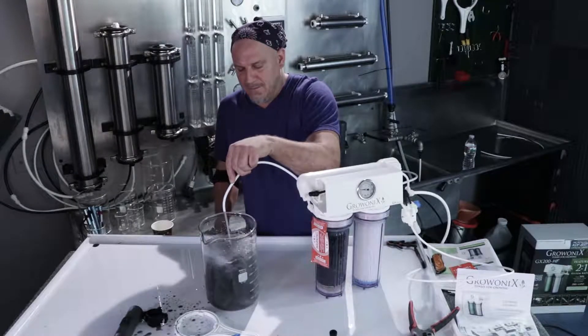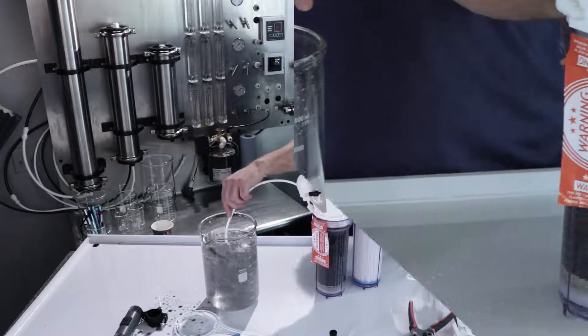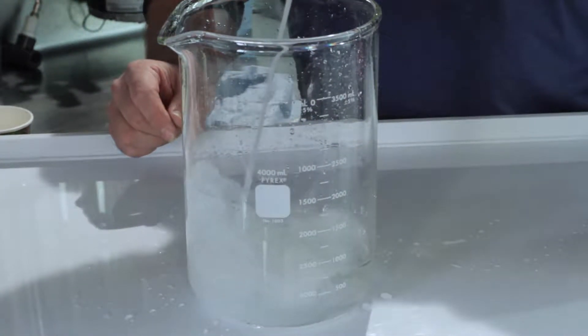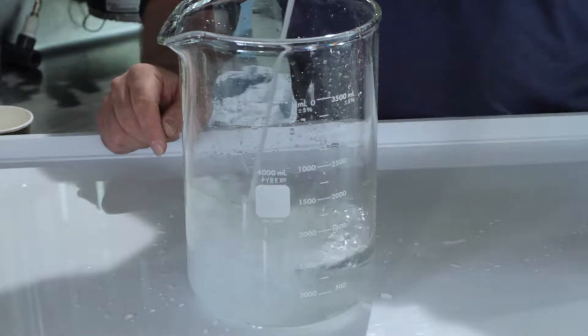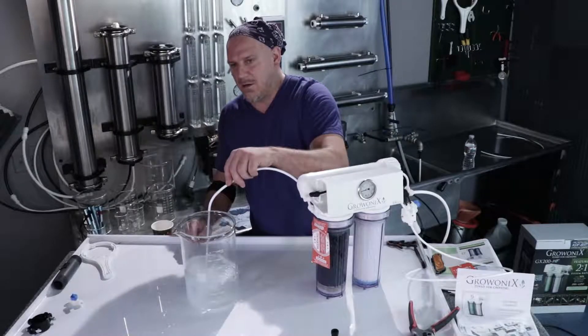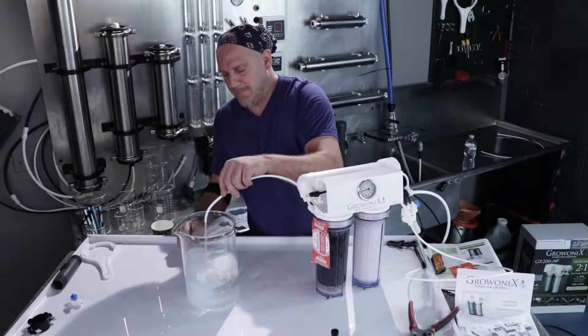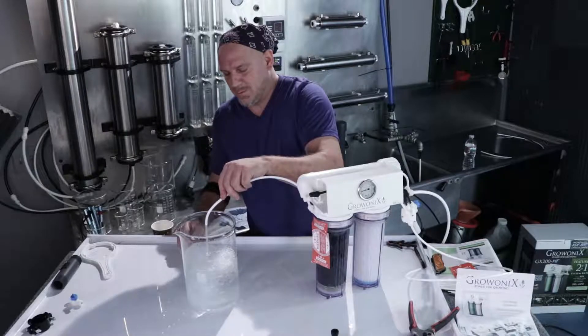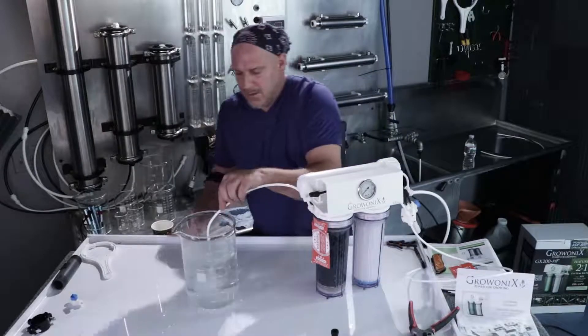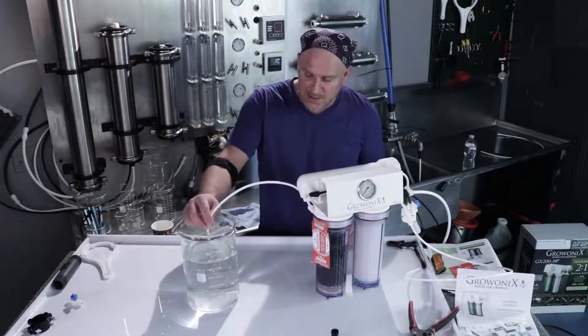You can see the stream cleaning up right now. As you can see, that stream is really cleaned up. There's a lot less air bubbles in it, it's almost perfect. I flushed about 10 gallons of water through this carbon already, and you can see the water is coming out clear. Now you can be confident of plugging this tube back in and feeding a membrane that we've got all the carbon dust out.